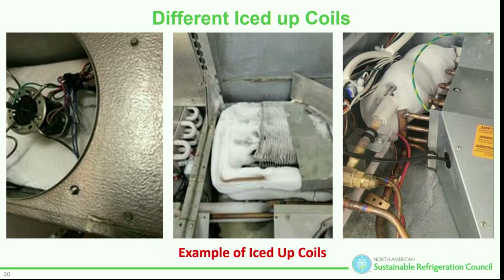Here are some examples of iced up coils. You can see that the frosting was starting to happen all the way back here. And if this is frozen, you can already assume that you have high superheat. Because if we're at negative 20 degrees saturated and I have nothing here, that tells me I have a crap ton of superheat going there.